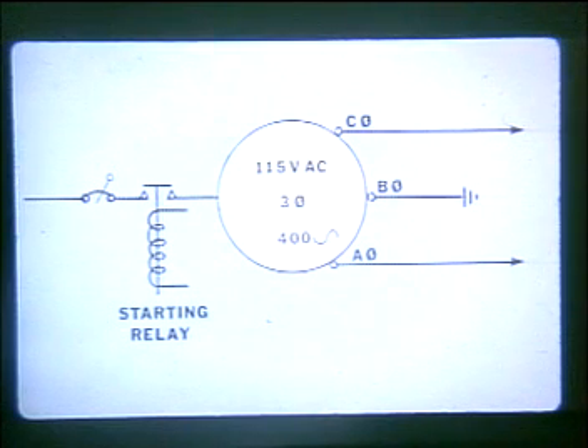The output of the alternator on the AC generator section of the inverter provides 115 volt AC 3-phase 400 cycle current. The phases are lettered A, B, and C. In the DC-6 aircraft, B phase is grounded to the aircraft structure. By utilizing connections from A to B, C to B, or A to C, we can obtain 3-phase or single-phase AC power as desired. AC equipment in the aircraft uses both single and 3-phase AC power. The A phase of both inverters is a regulated phase and is the voltage read in the cockpit on the AC voltmeter when the inverter voltage is selected.